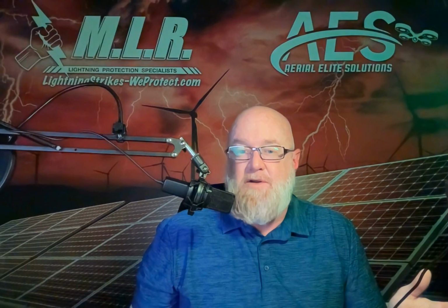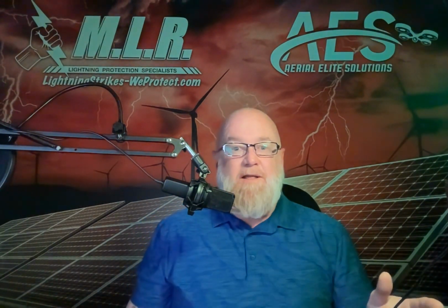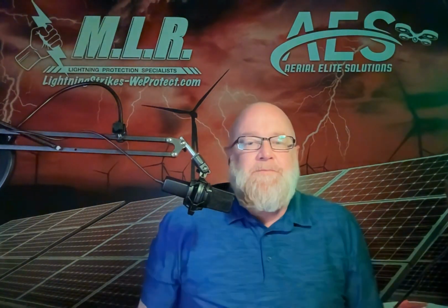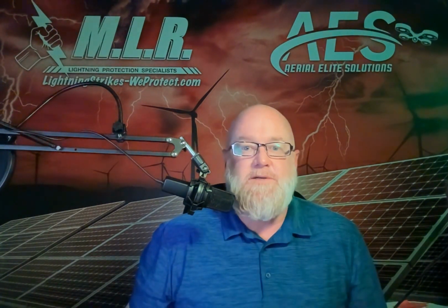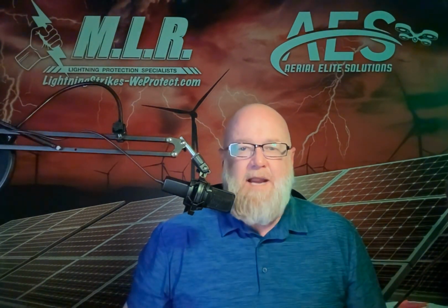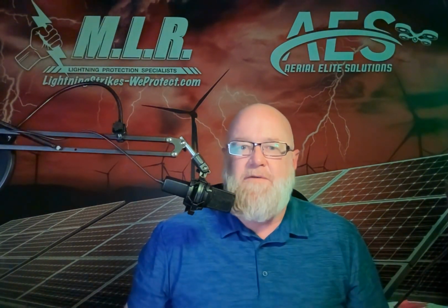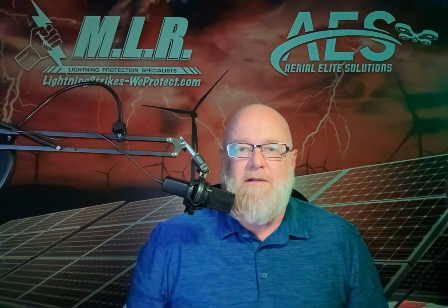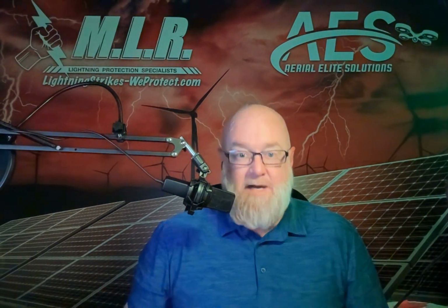So that being said, you could essentially have a huge structure that comes up to one big point, and one lightning rod can require, if it spaces out and it's 100 foot by 100 foot or whatever, 4 or 5 grounds just for one lightning rod. This is true. It's every 100 foot on average, which location can be juggled a little bit, but quantity can't be. So if it's 500 foot around the perimeter, there's got to be 5 grounds. If it's 510 foot around the perimeter, there's got to be 6 grounds.